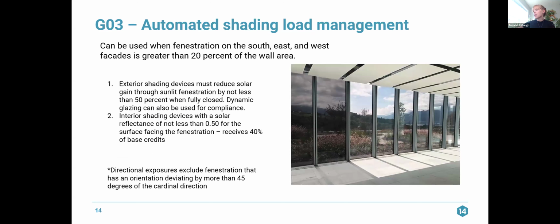G03, automated shading load management. Can be used when fenestration on the south, east, and west facades is greater than 20% of the wall area. So if we have a building design that has a greater than 20% window to wall ratio on the south, east, and west facades, you can achieve credits under this credit section. If you have exterior shading devices, they must reduce the solar gain through sunlit fenestration by not less than 50% when fully closed. Dynamic glazing could also be used to show compliance, and they would qualify under the exterior shading devices category. If you have interior automatic shading devices, they must have a solar reflectance of not less than 0.50 for the surface facing the fenestration. And you can only achieve 40% of the base credits.